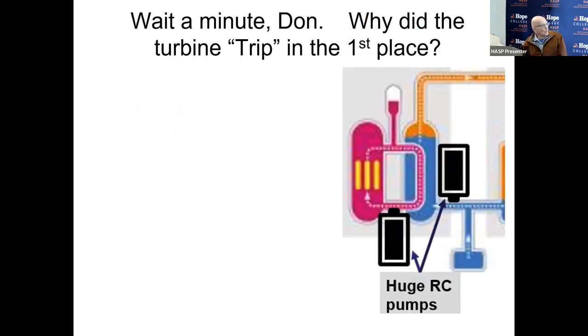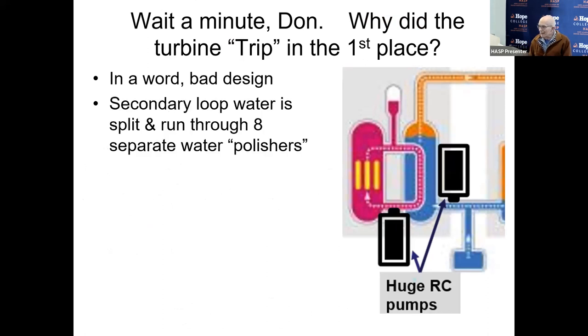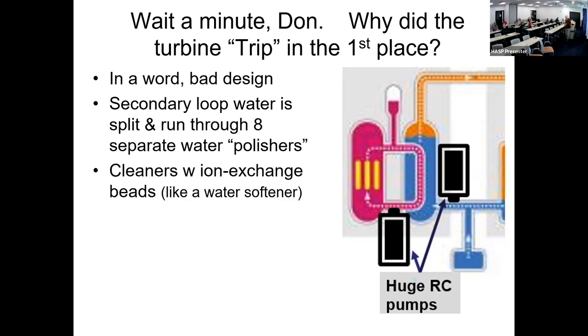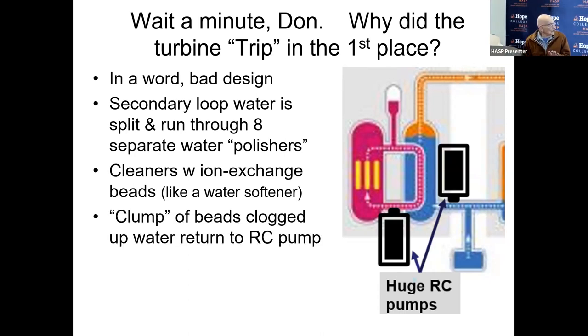Wait a minute, Don. Why did the turbine trip in the first place? In a word, bad design. That secondary loop water running by those thin-walled copper tubes like a radiator picks up debris, erosion, corrosion things. It's got to be cleaned. It runs through what are cleaners. No, in the business, we call them polishers. Ion exchange resins, little beads like a water softener, and it's going to collect these beads. Well, some of those beads clump up, and they clumped up and clogged a water return to the cooling pump.